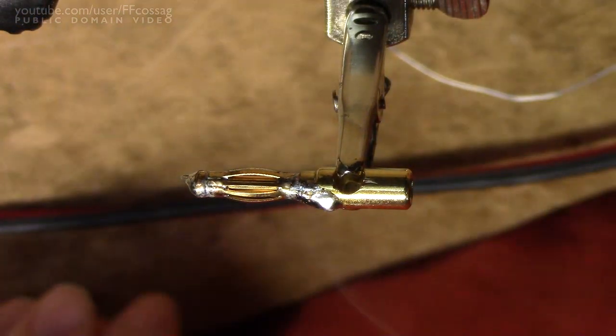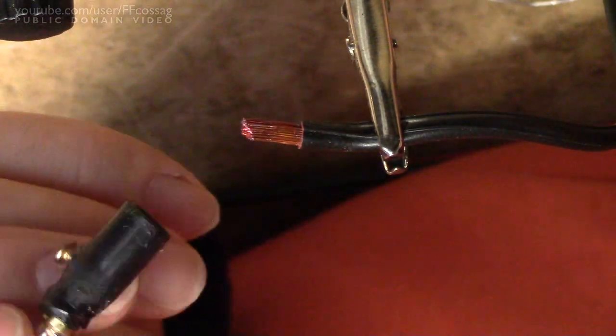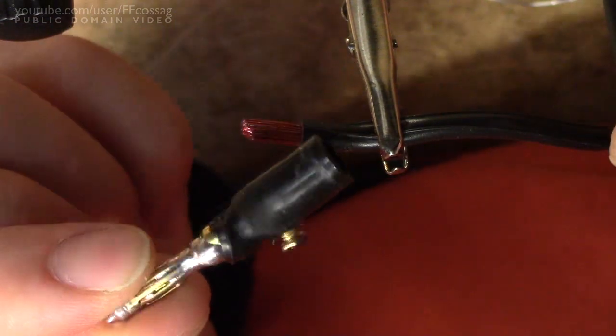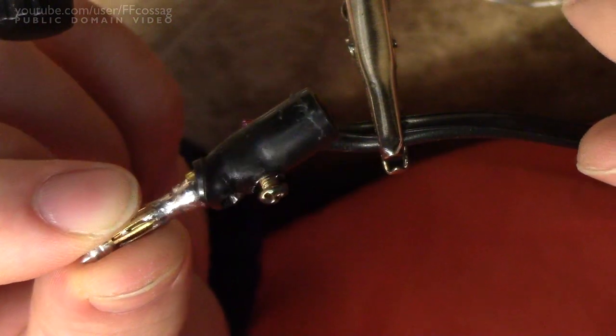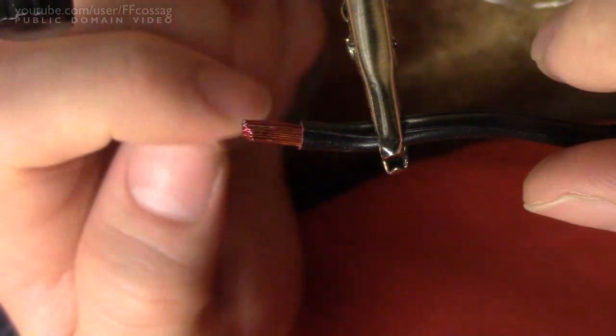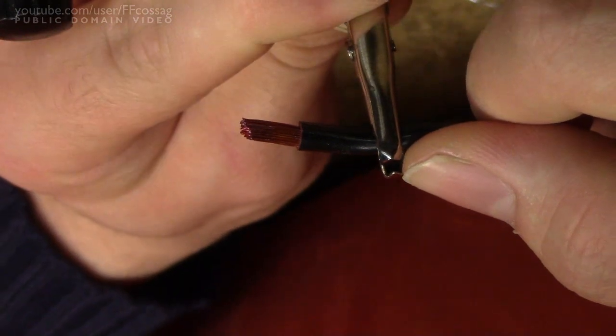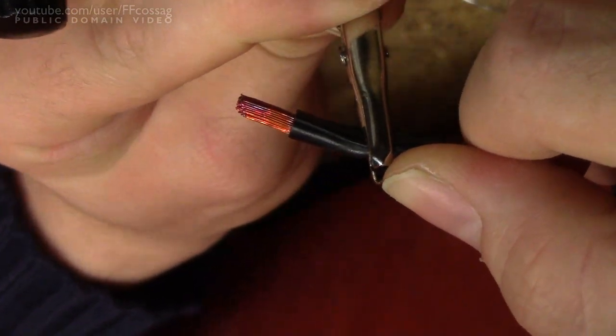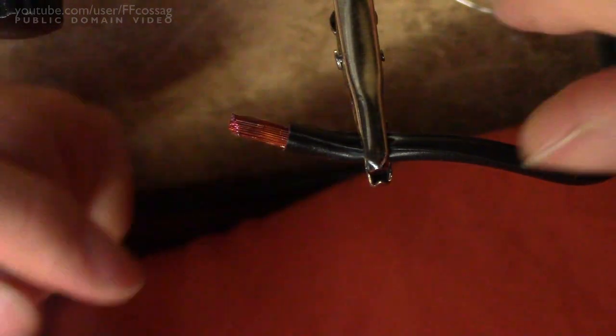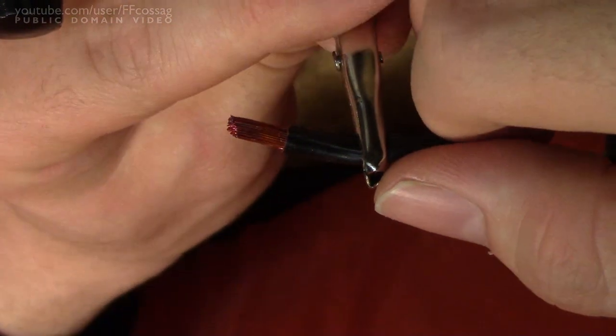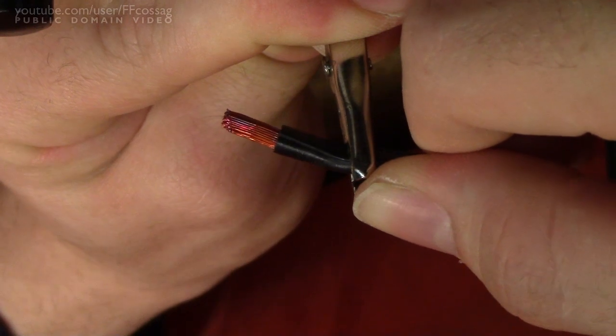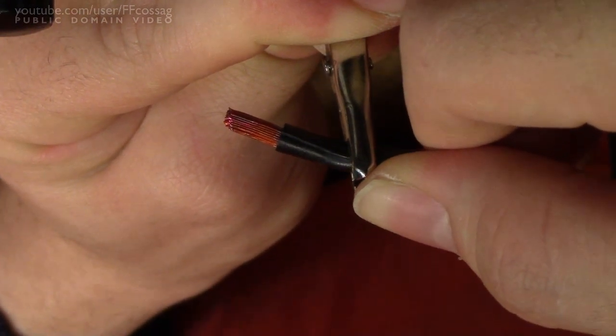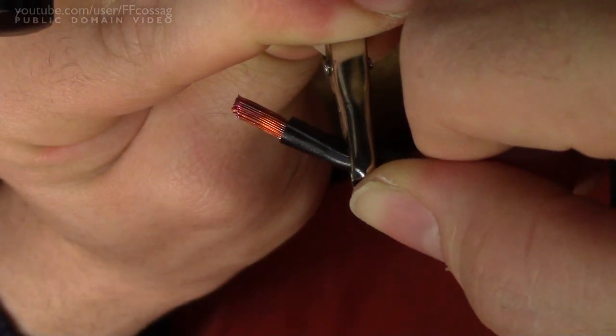Like so. Oh wow, I just removed the broken plug and just look at that melting there. The screw was all fused into the plastic, but above all, just look at the color of the copper. The wiring turned into the same color as my shirt, and this is not a copper colored shirt. That has run so hot. That's insane. This must have been like a couple of hundred degrees.